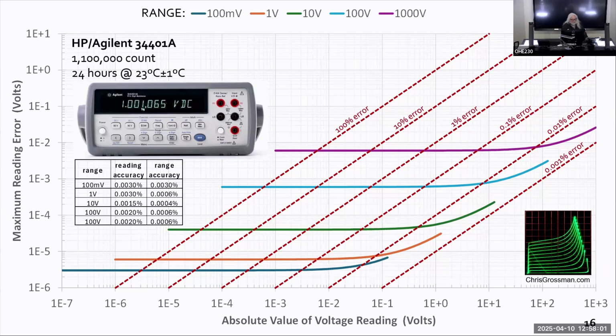The accuracy on different ranges, the way it's specified, is in that table - it's got a reading accuracy and a range accuracy. Notice the top range is the 1000-volt range. Let's look at the 10-volt range, the green one. At the top of the range, we see the range accuracy is 0.0004%, and you can see it bending over, with that asymptote going up to about 0.004%. That last line is 0.001.